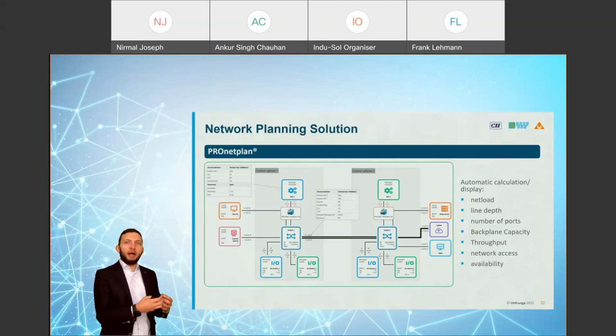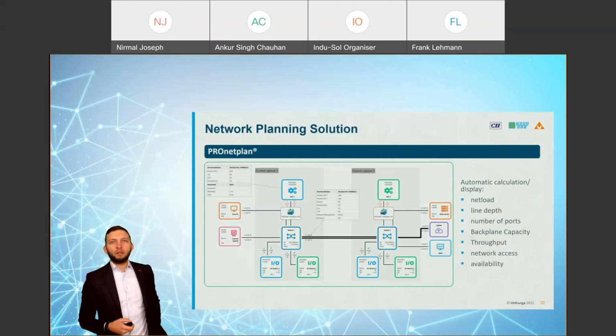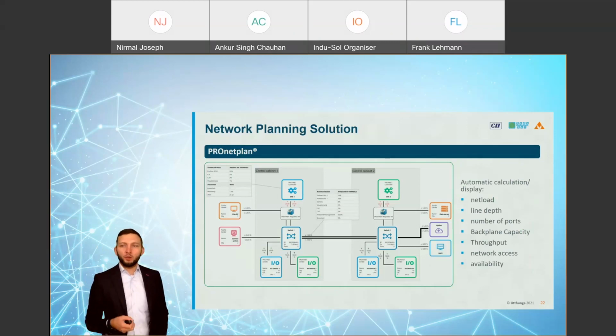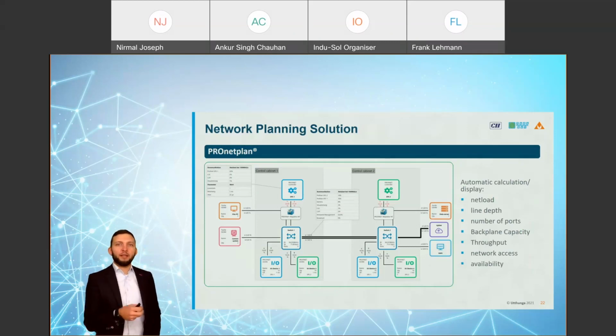I need a higher performance switch so it can handle the whole net load in my network. Therefore, we can describe backplane capacity, the throughput from the switches, so you have a parameter to select switches for your network. And at the end, network access, and we can also describe the availability of the network. This is a solution, it's an easy tool to use, and it's called PROnetplan.